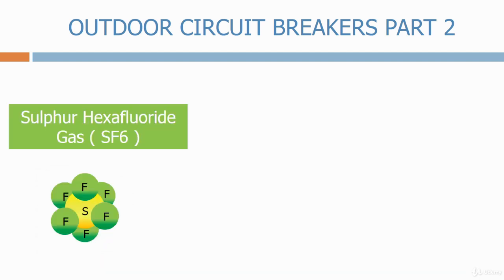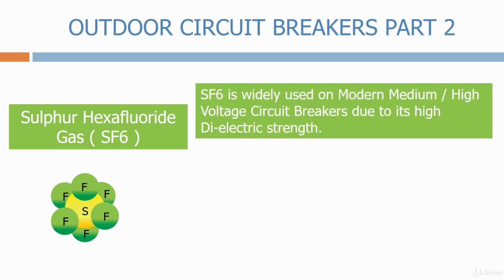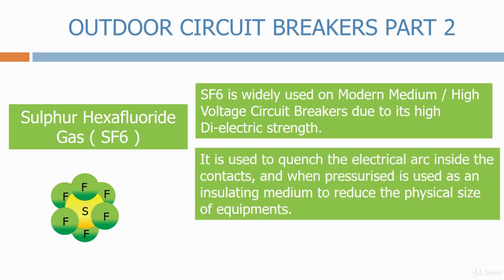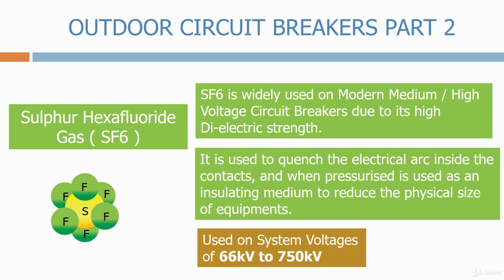Sulfur hexafluoride gas, or SF6. SF6 is widely used on modern, medium and high voltage circuit breakers due to its high dielectric strength. It is used to quench the electrical arc inside the contacts, and when pressurized, is used as an insulating medium to reduce the physical size of equipment. Used on system voltages of 66 kV to 750 kV.